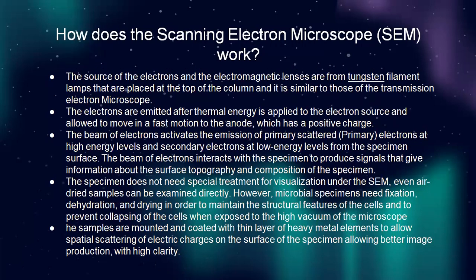Next, I will explain how the scanning electron microscope works. The source of electrons and the electromagnetic lenses — from tungsten filaments placed at the top of the column — are similar to those of the transmission electron microscope. The electrons are emitted after thermal energy is applied to the electron source and allowed to move at fast speed towards the anode, which has a positive charge. The beam of electrons activates the emission of scattered primary electrons at high energy levels and secondary electrons at low energy levels from the specimen surface. The beam interacts with the specimen to produce signals that give information about the surface topography and composition.